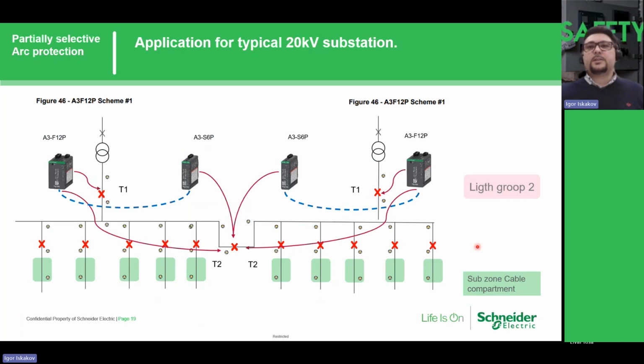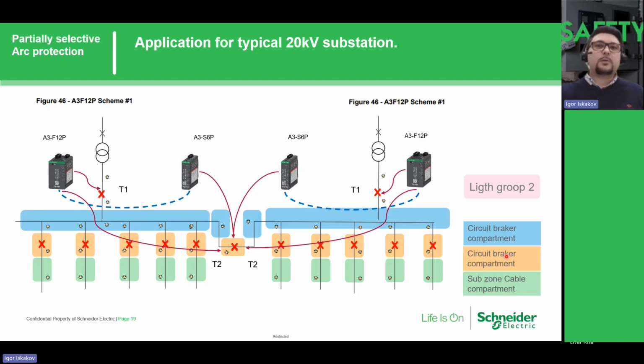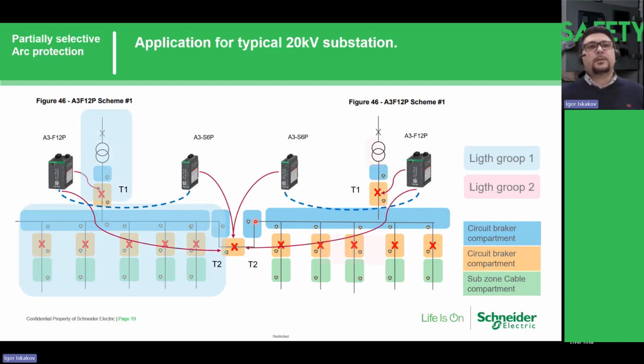So okay, here the same substation, a little bit changed, but the idea was the same. Here we can use partially selective arc flash protection. Before it was full selective protection, but here the cable compartment, circuit breaker compartment, and bus bar compartment are dedicated as one zone, for example, lighting group 1 and lighting group 2. This is the case when we have old switchgear and we don't have visible separation of the cable compartment. So in this case, the whole switchgear cannot be built selective, because the sensors in this circuit breaker will be dedicated to the flash in the cable compartment.